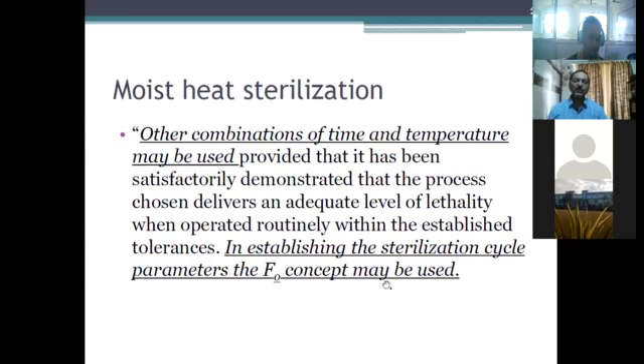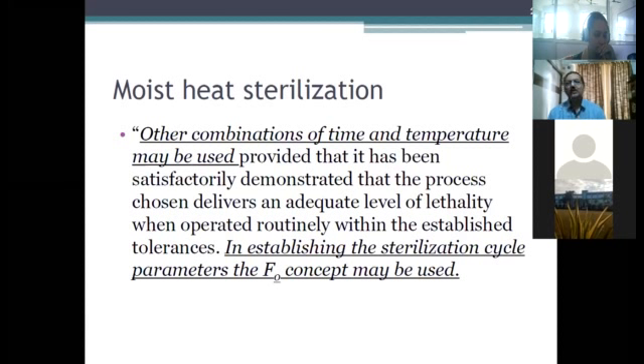So, whenever you are going to use any other conditions for sterilization which is not 15 psi, 121 degrees centigrade and 15 minutes, in such cases, the recommendations are that you should monitor the cycle using F0. Now, normally in our institutions, we do not monitor any cycle or we do not learn how to calculate the F0 value and to monitor any cycle on the basis of that. Whereas in the industry, many processes are such. Very common example I'll give you. All IV infusions packed in plastic bottles, which are usually 90% of products you see in plastic bottles these days.